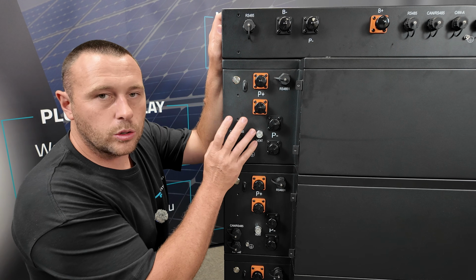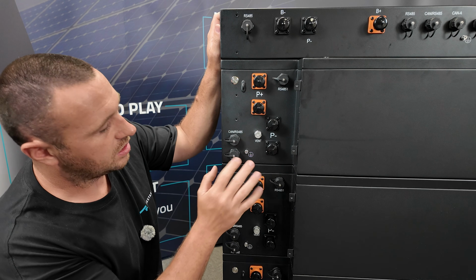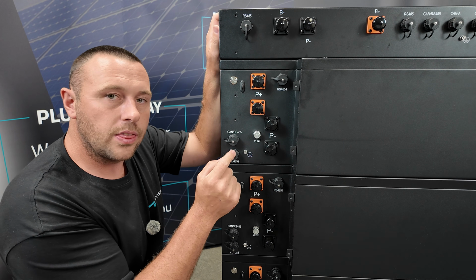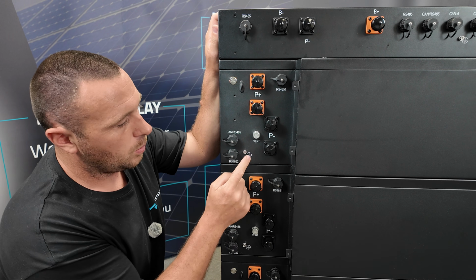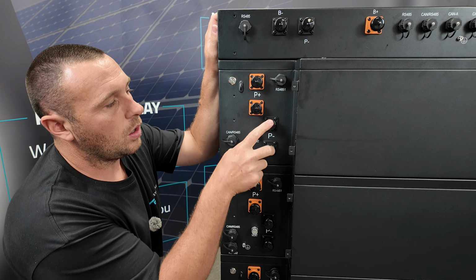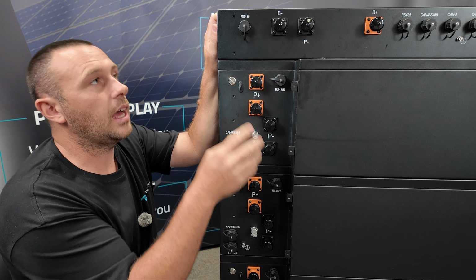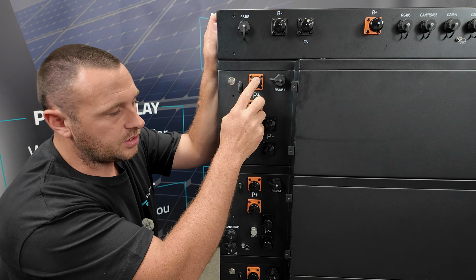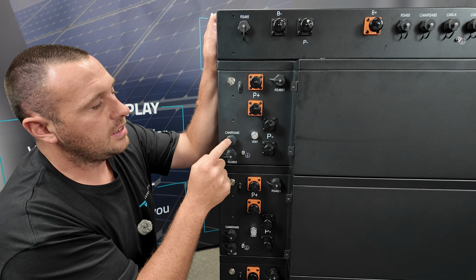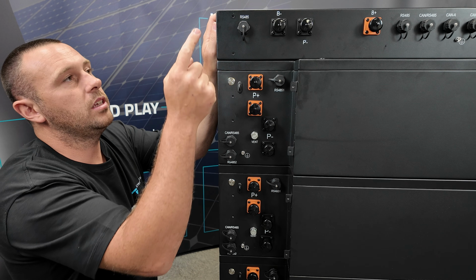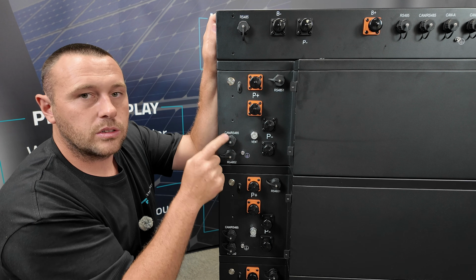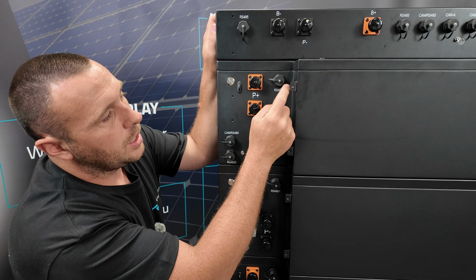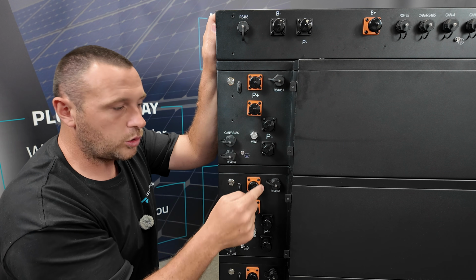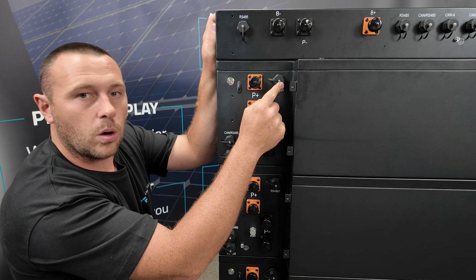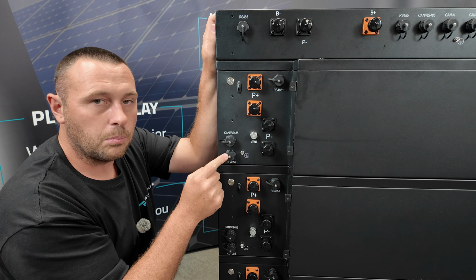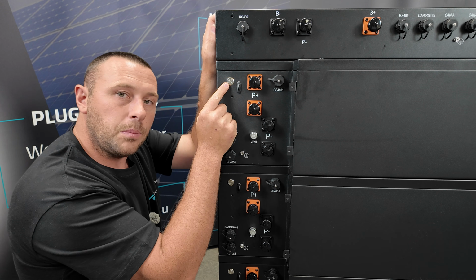And so on the back of the battery modules themselves, they're all exactly the same, they're all identical. So starting at the bottom here, we have the RS485-2 port. This is for module to module communication. We have another earth screw here, and these are the parallel connection cables between modules and the top control board. We've got the same with those with the positive. There is a battery vent. This is the CAN RS485 port, so this is what talks to the top control module, and that will only be used for the top stack battery. Then over here we have RS485-1. Again, this is for module to module communication. So RS485-1 goes to RS485-2 on the module above it. And then the only other thing here is the power button.